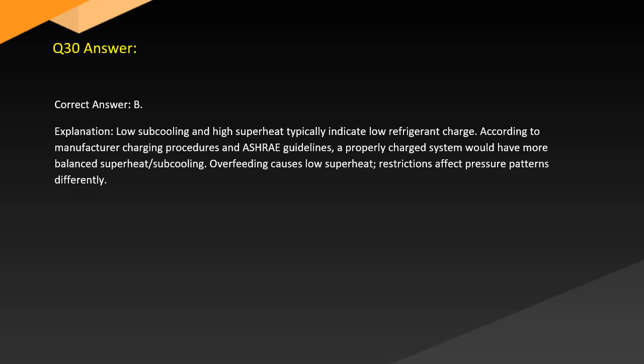Answer. Correct answer B. Explanation. Low subcooling and high superheat typically indicate low refrigerant charge. According to manufacturer charging procedures and ASHRAE guidelines, a properly charged system would have more balanced superheat and subcooling. Overfeeding causes low superheat. Restrictions affect pressure patterns differently.